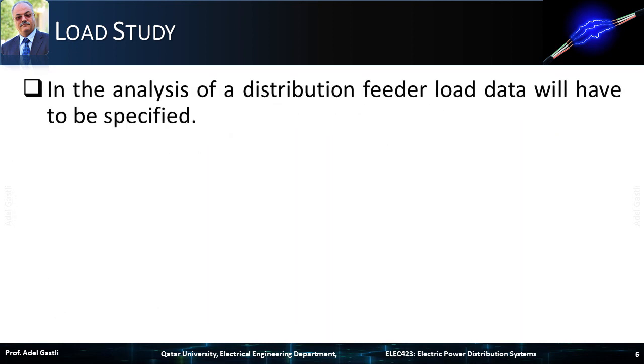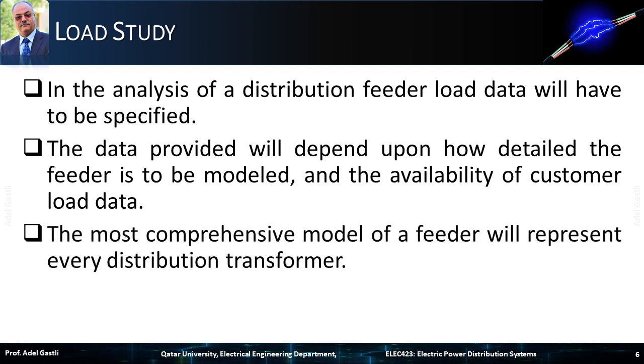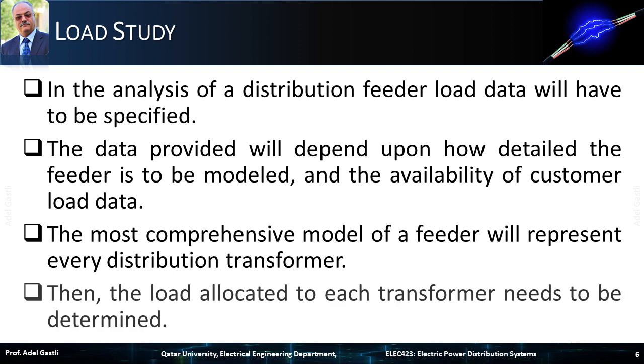In the analysis of a distribution feeder, load data will have to be specified. The data provided will depend upon how detailed the feeder is to be modeled and the availability of customer load data. The most comprehensive model of a feeder will represent every distribution transformer. Then the load allocated to each transformer needs to be determined.